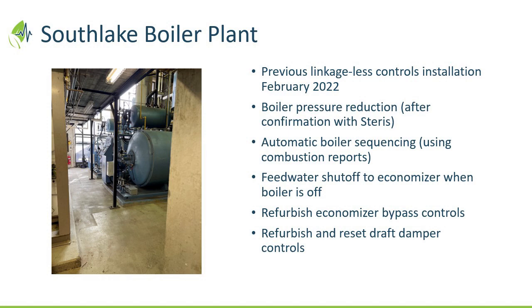The automatic sequencing, when we look at the boilers, you can tell us, Paul, where we see that, and you can explain how that benefits. So when do you switch from one boiler to two? It's a big decision, it matters. It's looking for the sweet spot on efficiency. This idea of the feed water supply to the economizers, love you to explain how would that be done. So, an economizer is the feed water goes through the chimney, the stack, before it goes to the boiler and recovers heat. But when the boiler's not running, it's giving heat up. And as Paul mentioned, the draft, that heat then goes up the chimney and goes away. So shutting that off. So fairly simple conceptually, but technically how does it happen?